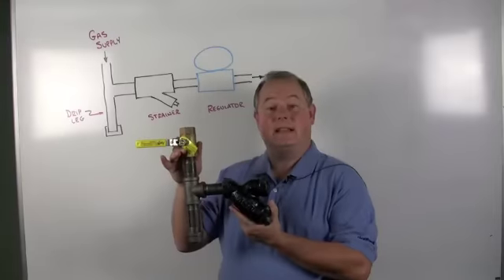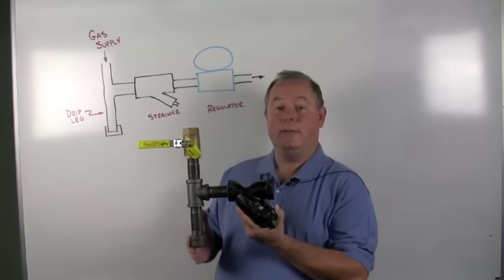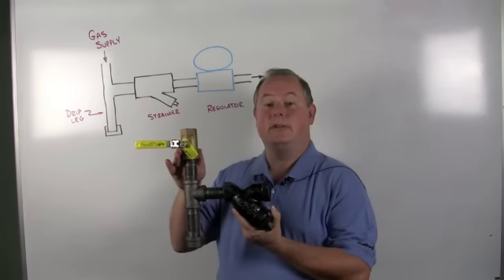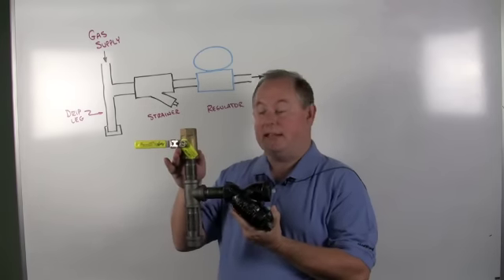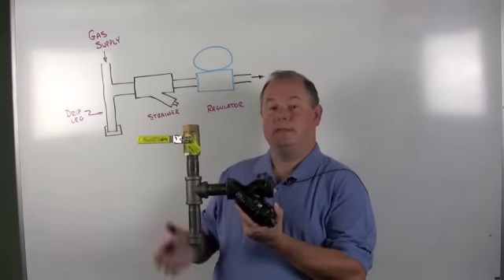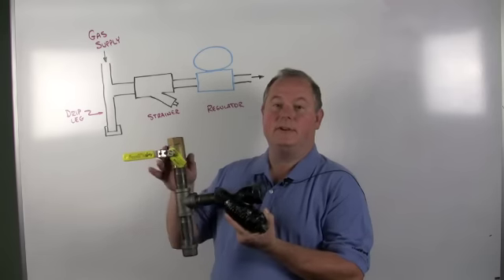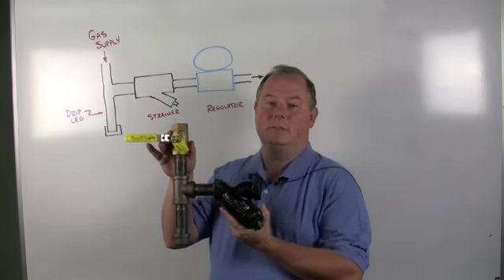Here's the piping setup we've been talking about. Gas supply in here, the drip leg that you need, the Y strainer. Do yourself a favor when you have the compressed air on for the pressure test. When you relieve it, relieve it through the cap on the leg or the plug in the strainer. Let it do the work to clean the debris out of the system.